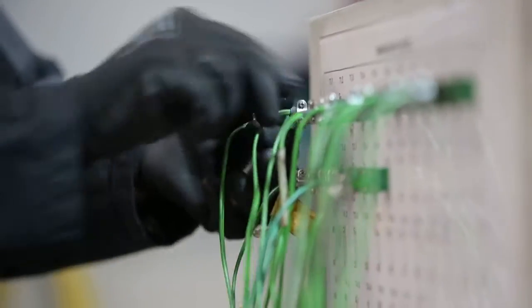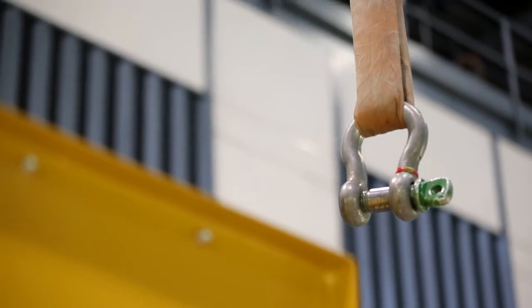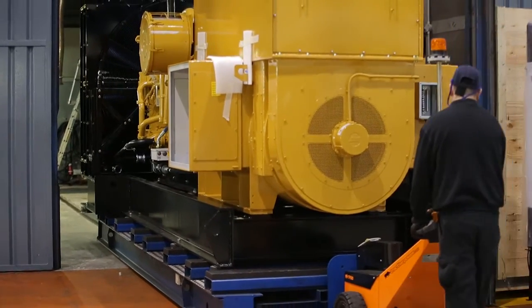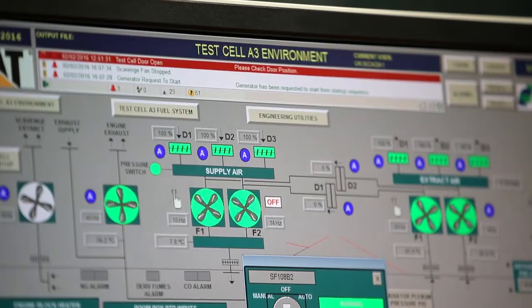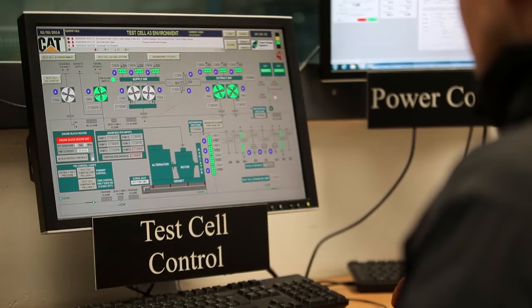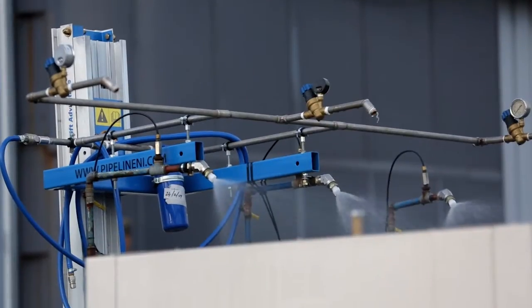Utilizing up to 12 megawatt resistive capacity, a 3 MVA inductive capacity and a 750 kVA capacitive capacity. In addition, we have the ability to test medium voltage generator sets and multiple units synchronized together running with their associated control and switchboard equipment, simulating site conditions and installations.